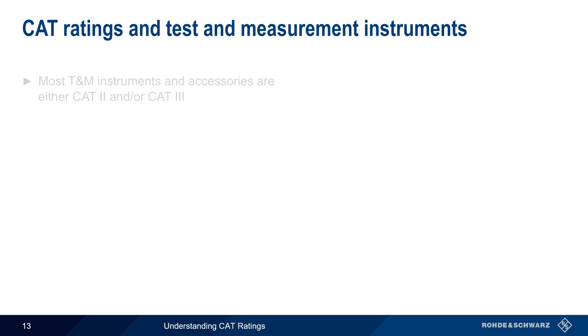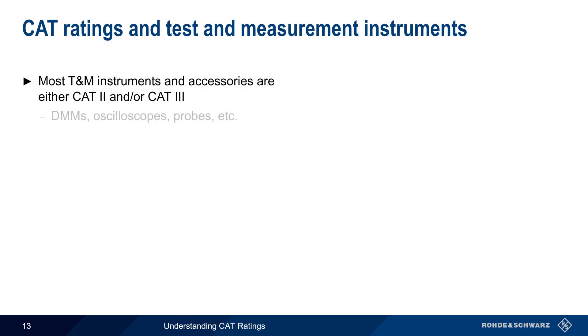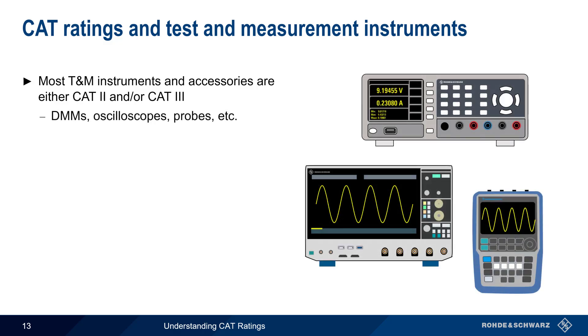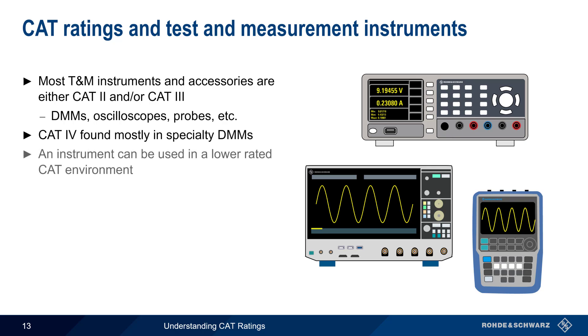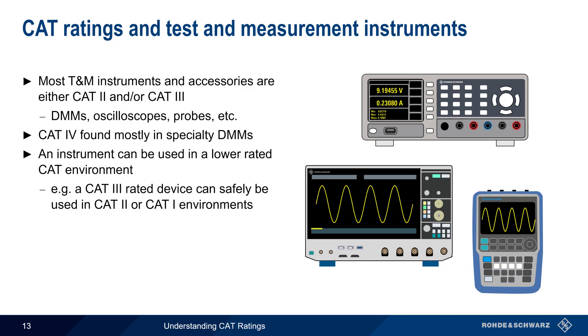Most test and measurement instruments and accessories are either CAT 2 and/or CAT 3. This includes digital multimeters, benchtop and portable oscilloscopes, probes, etc. CAT 4 is generally found only in some specialty DMMs designed for higher voltage work. Note, however, that an instrument with a given CAT rating can be used in lower CAT environments. For example, a CAT 3 rated device can be safely used in a CAT 2 or CAT 1 environment, assuming that the maximum rated voltage is not exceeded.